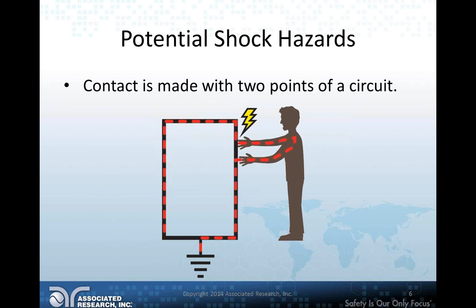However, you don't always have to be at ground potential for there to be a shock hazard. Contact made between two points of a circuit is also a shock hazard. The person is not at ground potential, but they are a low enough resistance path that across those two hands, the current takes that direction. That path is particularly bad because you're going through the chest cavity, and there are different effects depending on the level of current and voltage that electricity has on the human body, which we'll cover in a few minutes.